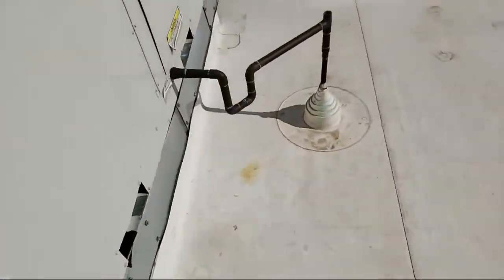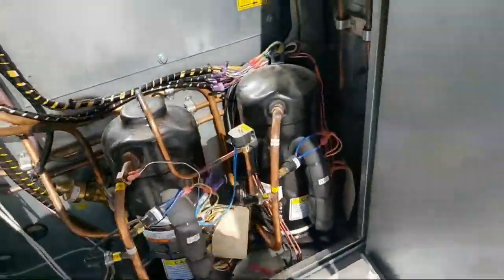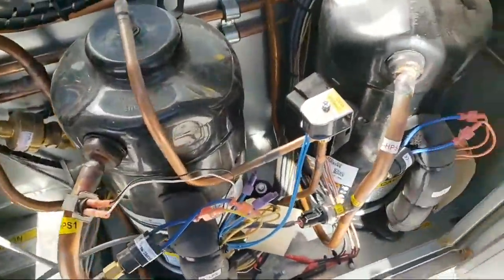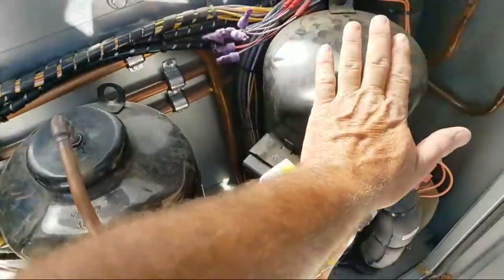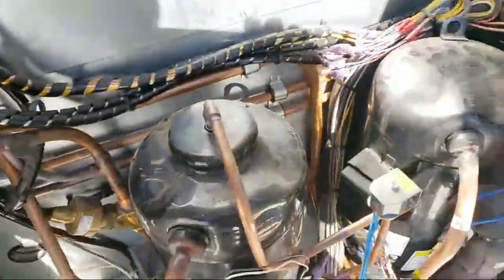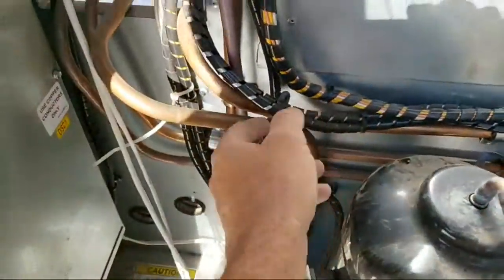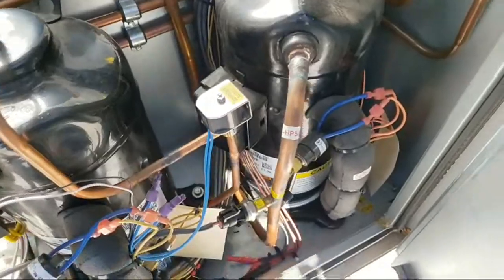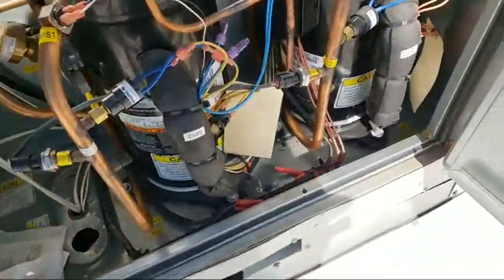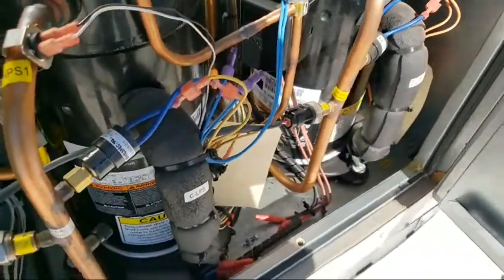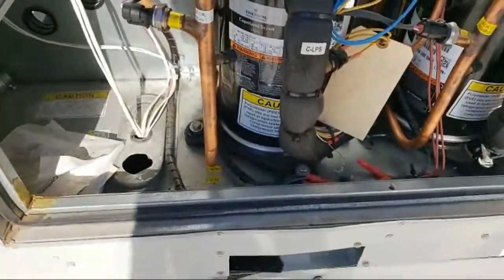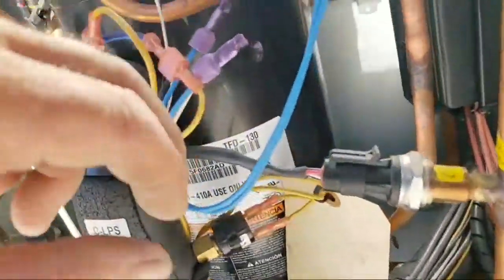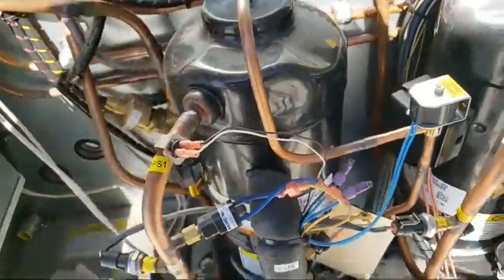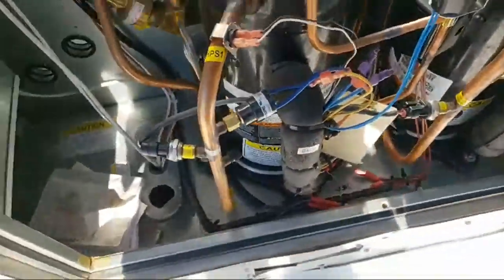It is considered a heat pump, though. Although I don't see a changeover valve on the second compressor. Hot gas pipe. Yep, it's cooling only, it looks like, for the second compressor. Another 67,000 BTUs. Primary one is 61,000 BTUs, basically about 5 tons, big 5 tons. So only the first compressor has a changeover valve.